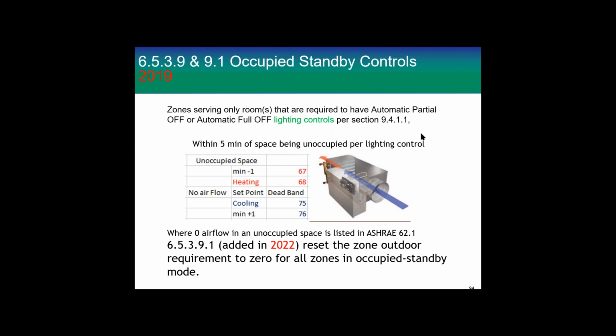Now, we only required you to go -1 or +1 because we had to get this adopted. But, as the designer of record, and your customer, what happens is they come back into the room, and the system starts back up, and it takes a minute or two to get back to set point. So you can say, well, my people could stand 3 degrees or 4 degrees or something. It doesn't have to be just 1 degree in the dead band, and they would still be happy, and you can save more and more energy. So this is an individual box serving whatever it's serving, individual zone.